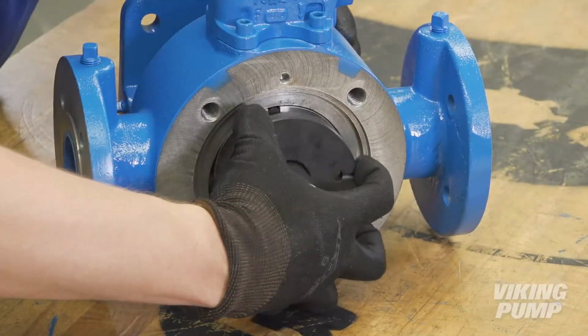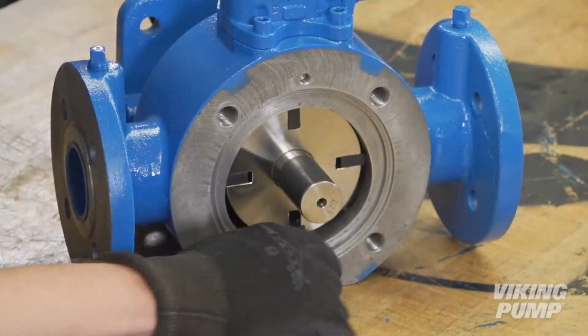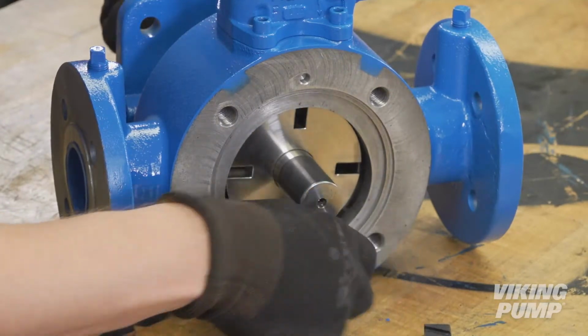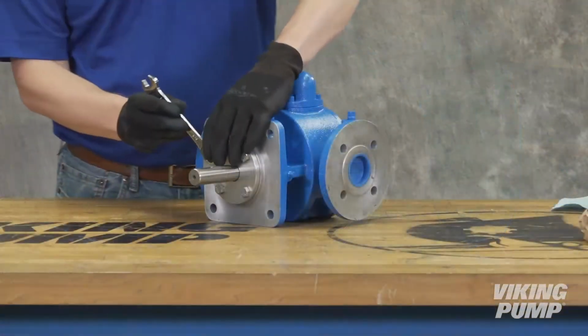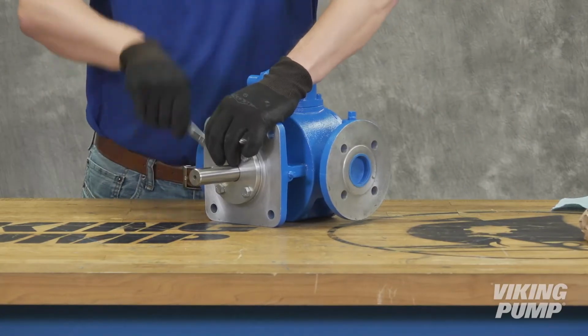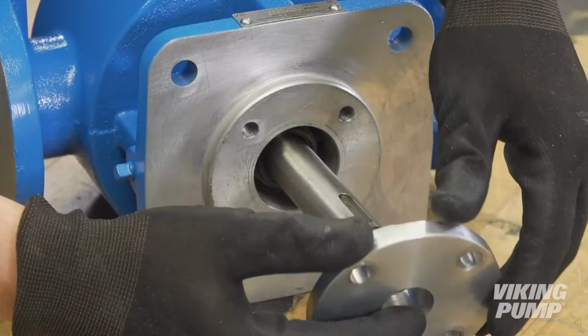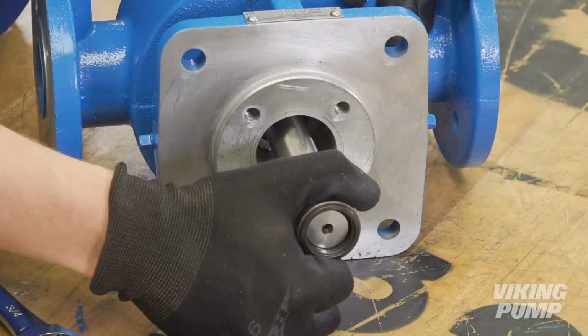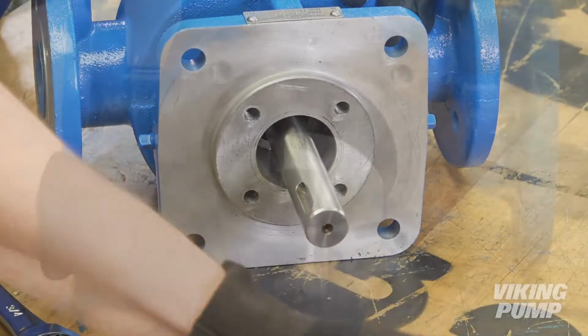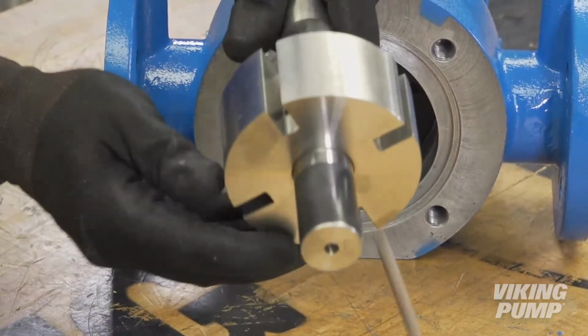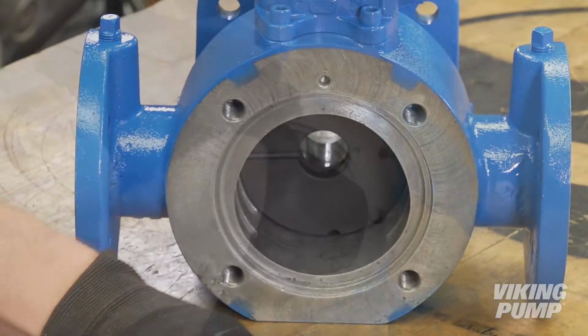Next, the pump needs to be disassembled. Begin by removing the first carbon disc and sliding vanes. For seal removal, please refer to our component and cartridge seal replacement videos. Then you may remove the rotor shaft, push rods, and second carbon disc.